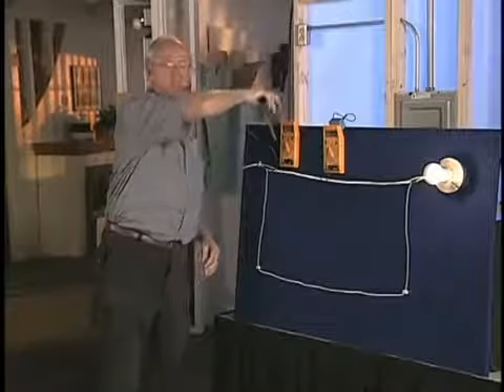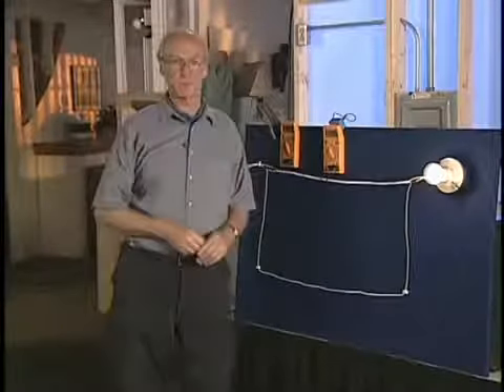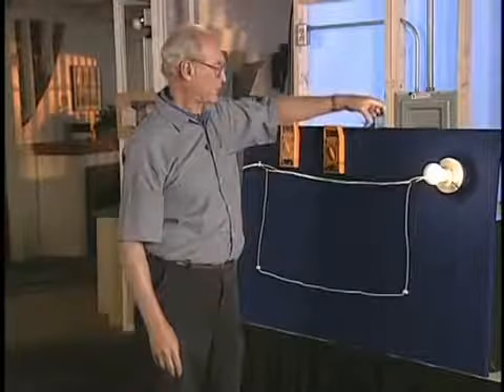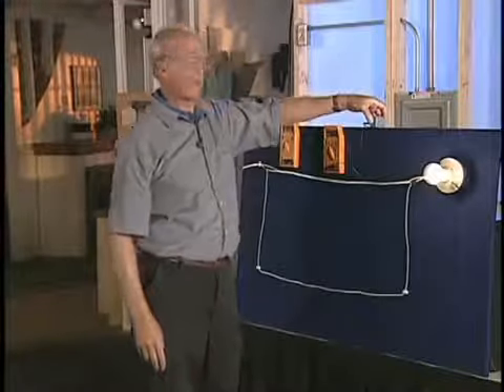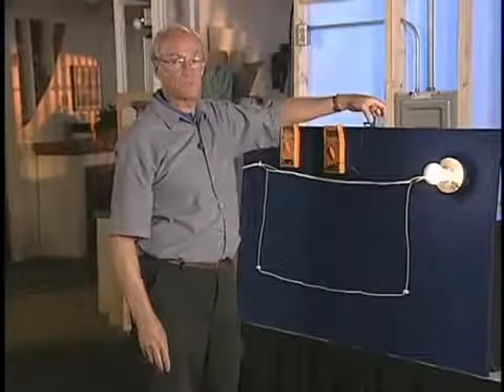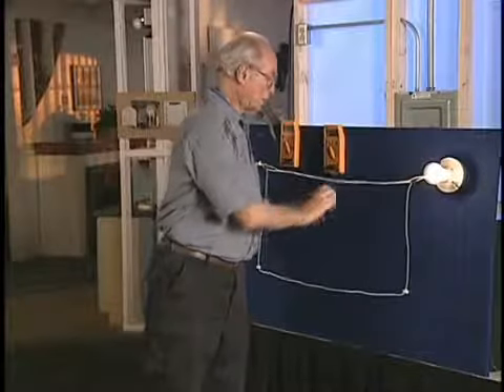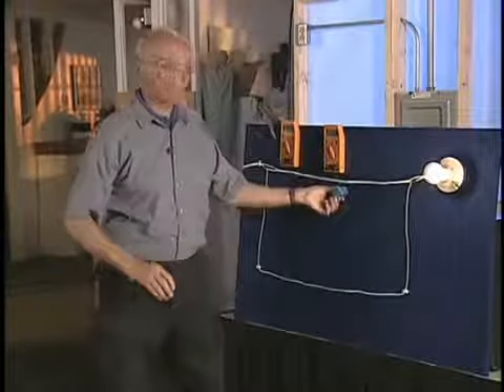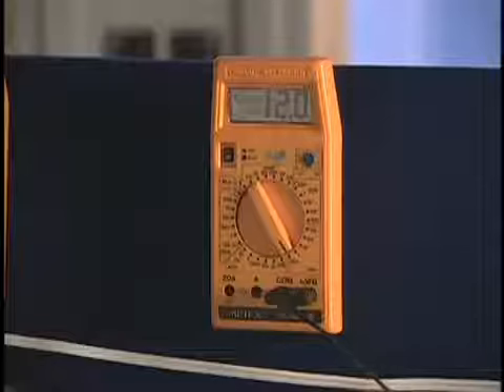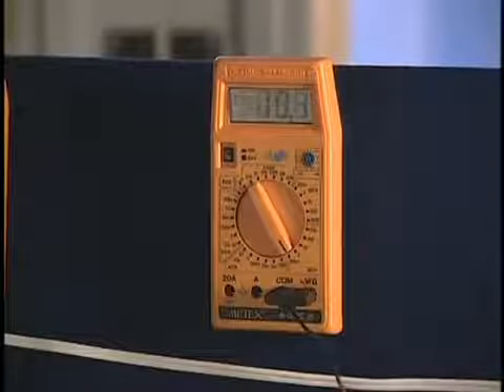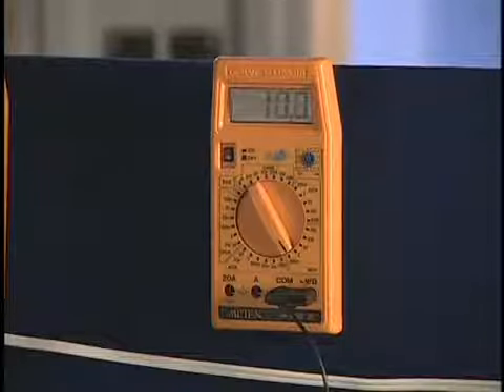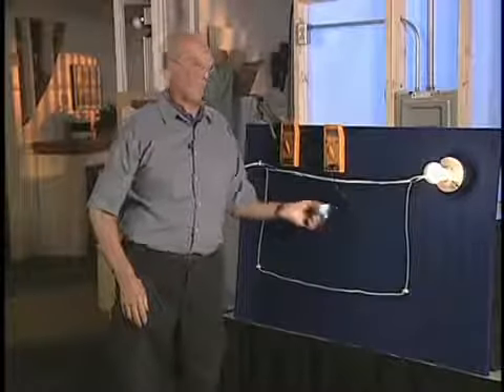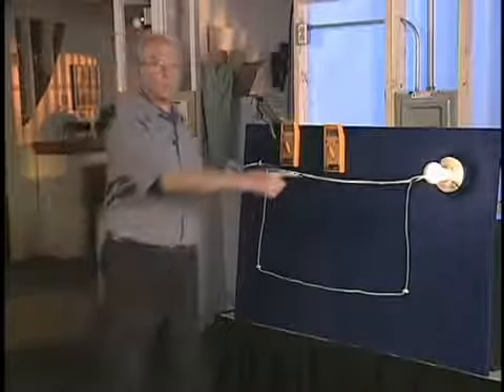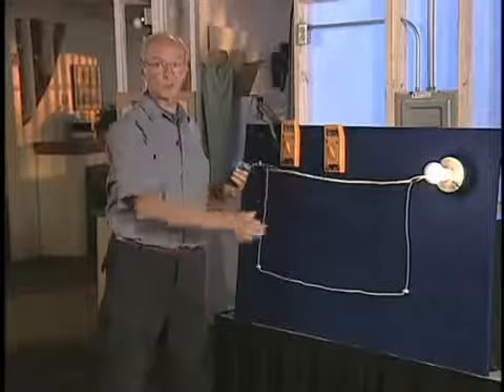Now let's see what splitting the neutral current does to the magnetic field. Before paralleling, our Gauss meter measured 0.2 of a milligauss at 6 inches from the cord. Now it measures 1.9 milligauss. Now if we put the Gauss meter probe inside the loop and move it across the loop, we note that the field maintains a high and fairly constant level. Inside a school, a series of classrooms could be enclosed by such a loop.